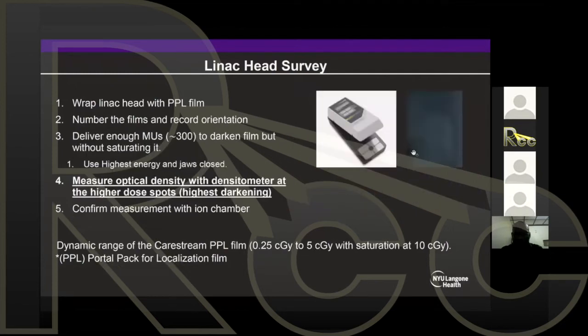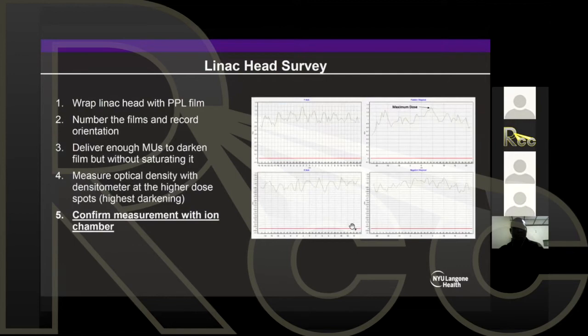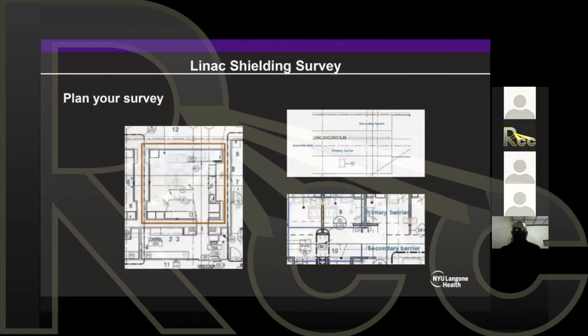Then you look at the spots that get darker, and you measure with a densitometer only in those highest darkening spots. And then finally, you can confirm with the ion chamber. In our case, we use an ion chamber profiler. So we have more of an area, and you verify where you have your maximum dose, and that around the area the numbers make sense, that you are within that limit. Okay, so now we're going to go to the proper Linac shielding survey. So first thing, of course, plan your survey.